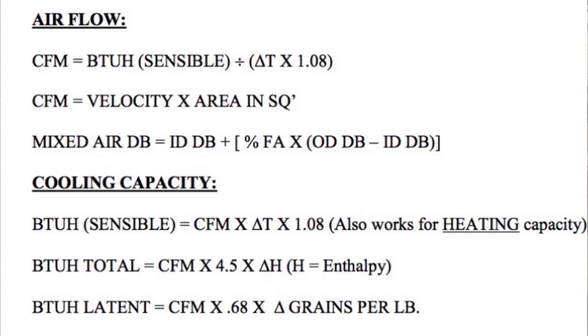That gives us 37,800 BTU — and it's just that simple. If you have those measurements you can do that. It works in reverse too: if you have a known output you can work backwards to get your CFM, just like the airflow formula at the top. You can use these quite a bit. This one is just for sensible heat.